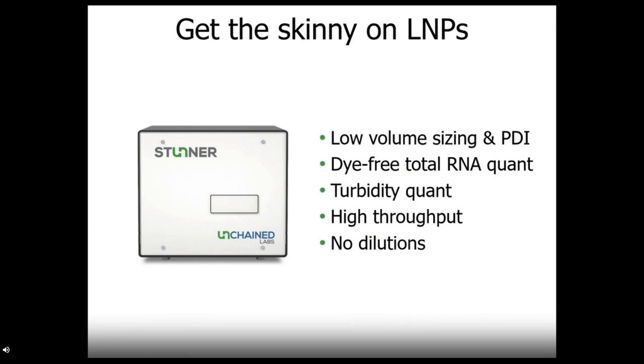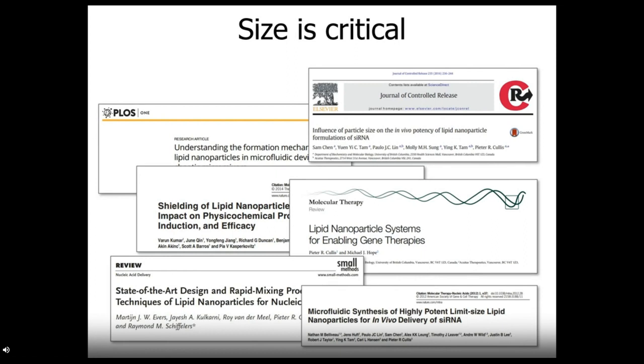Now, let's take a look at our applications. First, our completely new RNA LNP application. Without the need for dilutions, reagents, standards, or fluorescent dyes, you'll get size, polydispersity index, total RNA quant, and quantification of turbidity.